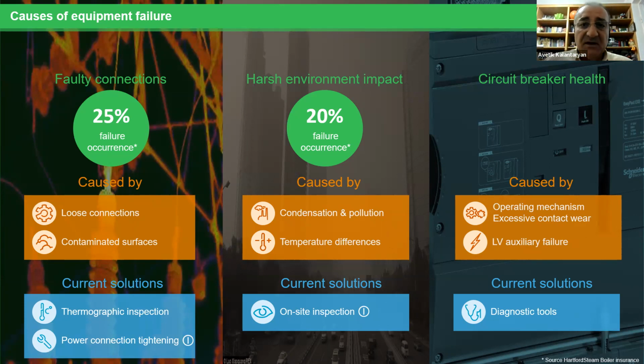Or harsh environmental impact: 20% of failures are caused by condensation and pollution from air, dust, dirt, and temperature differences in the equipment room or outdoor locations. Circuit breaker health is the most important factor for proper operation. Bad situations and faults are caused by operating mechanism issues, excessive contact wear, and low voltage auxiliary failure.